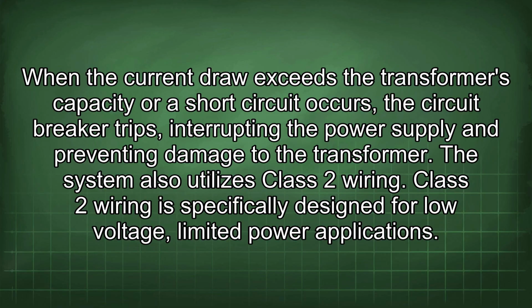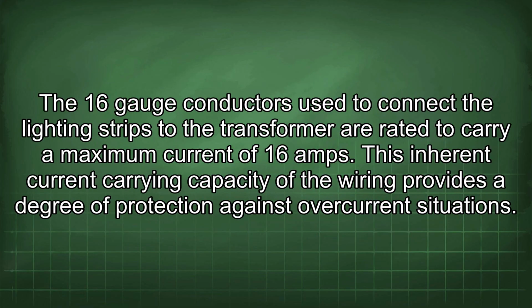The system also utilizes Class 2 wiring. Class 2 wiring is specifically designed for low-voltage, limited power applications. The 16-gauge conductors used to connect the lighting strips to the transformer are rated to carry a maximum current of 16 amps. This inherent current carrying capacity of the wiring provides a degree of protection against overcurrent situations.